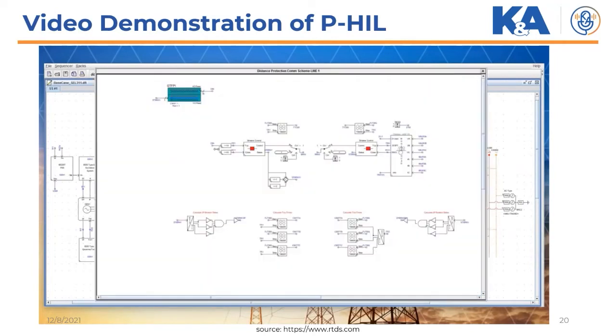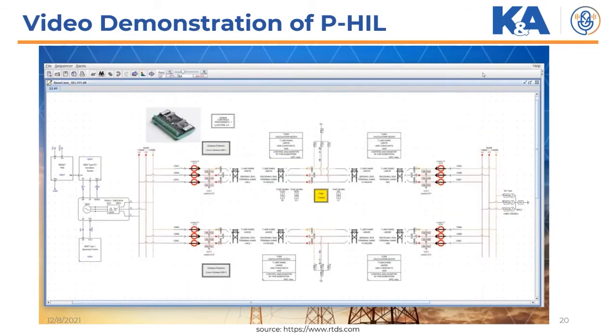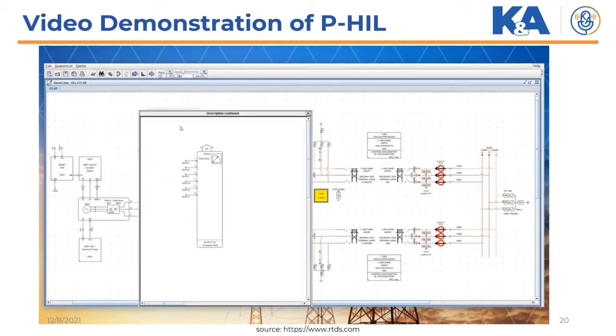Circuit breaker 1 is controlled by a software relay, simulated in RSCAD. This distance protection module is available in the RSCAD component library. Circuit breaker 2 is controlled by the physical relay connected to the simulator. The analog output component defines the signals that will be sent out of the simulation via amplifiers to the relay.